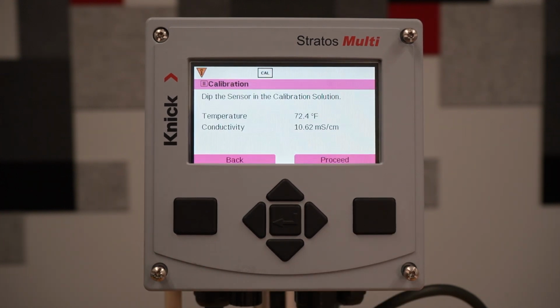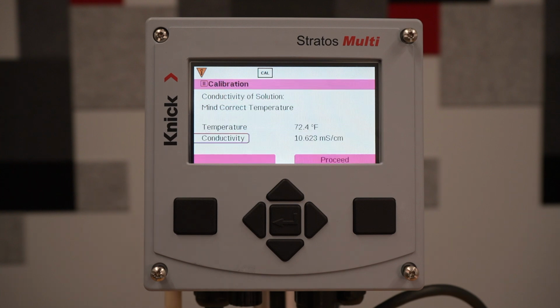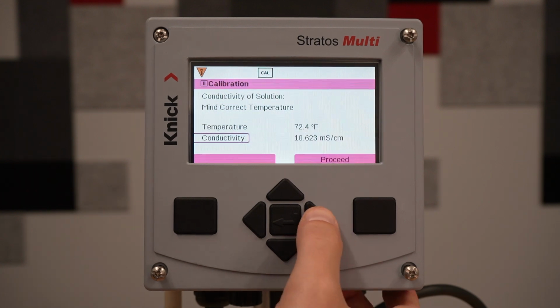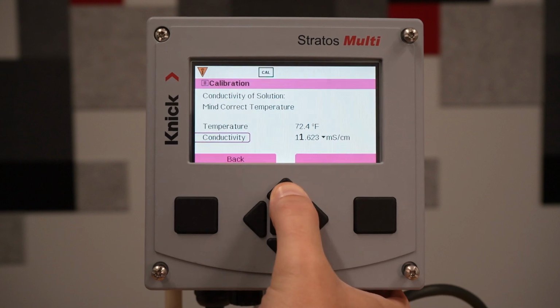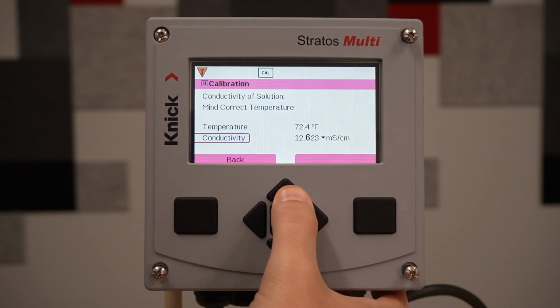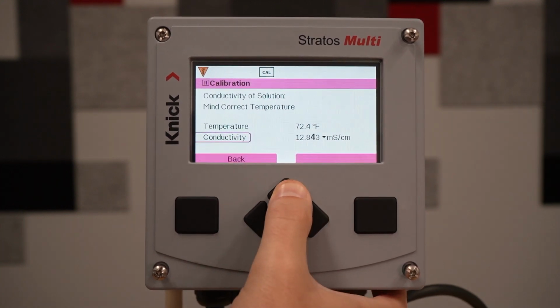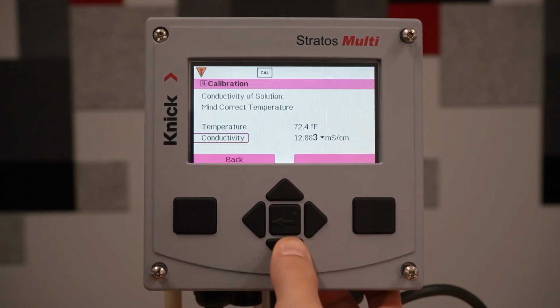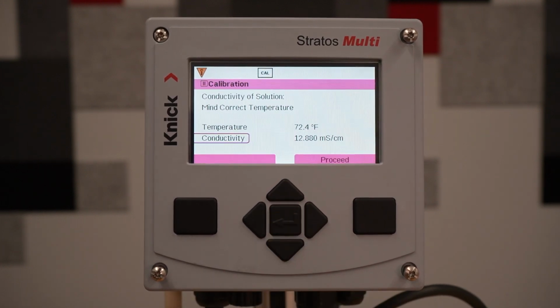We'll have our sensor immersed in the calibration solution. For this video, we are using a 12.88 millisiemens solution. We'll then hit Proceed. The drift will be checked, and the response time will be checked as well. Now, once this is done, I will use the right arrow key to manually set what the buffer solution was, which again was 12.88. I will then click Proceed.